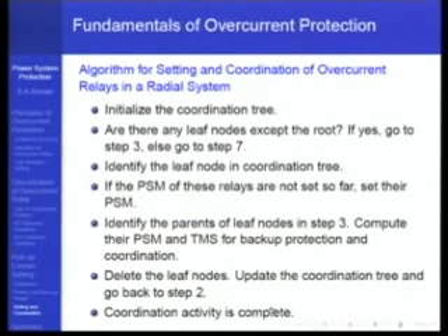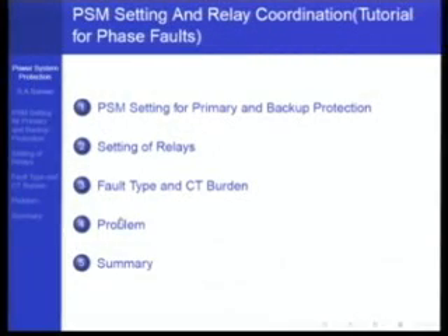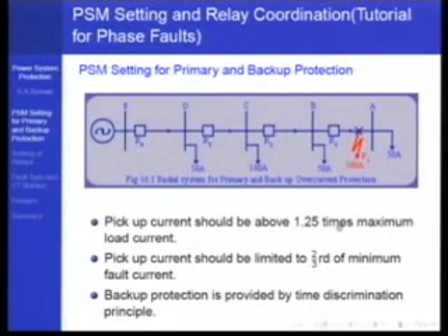So the same thing is mentioned here, so we will take one example now. PSM settings for primary backup protection, setting of relays, fault type, CT burden, primary pickup. Okay, this is the example problem. So what do you see in this example problem? You see that this is a radial kind of system. R1, R2, R3, R4 have to be set. Our guideline is pickup current should be above 1.25 times the maximum load current. Pickup current should be limited to 2/3 of the minimum fault current, so that you will always get a PSM which is greater than or equal to 1.5. So you don't have to worry whether you are working with numerical or electromechanical relays. As I said, PSM of electromechanical relays should not fall below 1.5, because the manufacturer does not guarantee the operating time below that region, even though it's shown on the curve.